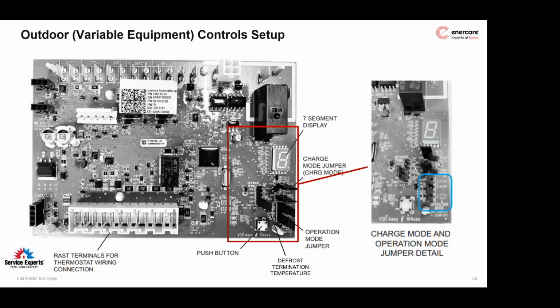And then for the variable speed compressor equipment, there are a series of selectable suction pressures, basically. The good news is, I would just leave them where they are. You don't need to change anything. There's an efficient mode, which is the most efficient mode. It will variably follow the outdoor temperature and adjust the suction pressure accordingly. There is a normal function, which locks the suction pressure in at 135 psig, so that at whatever temperature it is outside, you're consistently getting 135 psi.